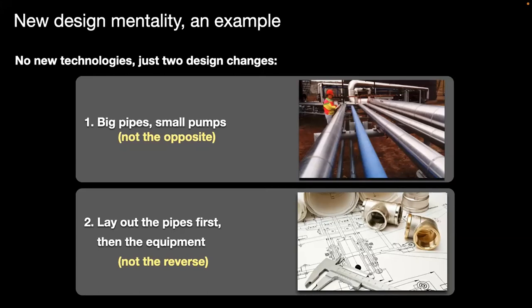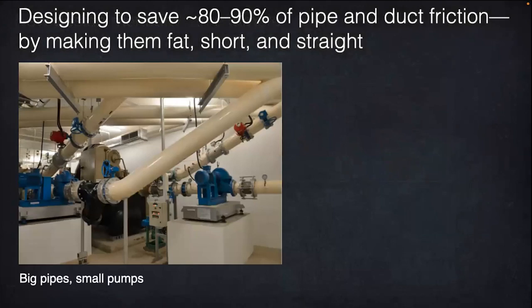But for you as owners, it's smarter to make pipes fat, short, and straight than skinny, long, and crooked. So low friction pipes make the blue pump on the right so tiny it looks like somebody slipped a decimal point, but they didn't. And you notice it's raised up on a plinth to meet the pipe rather than conventionally dipping the pipe down to a pump on the floor.